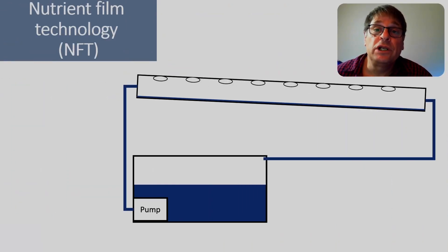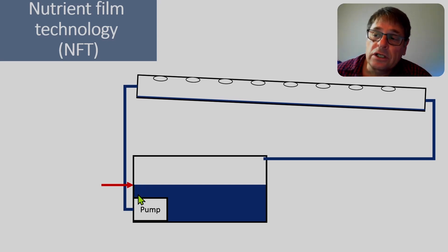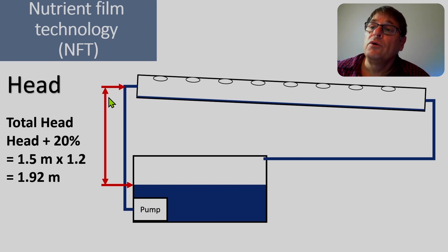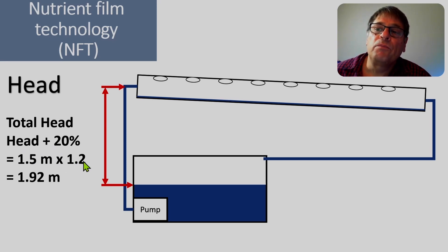Now we need to consider how high we must lift the water in the system. Remember, it's from the lowest point the water can reach up until the highest point where the pump must take the water. If you think your point is a little bit lower, move your measurement from there up to the highest point that the water must be lifted — not the highest point in your system, but the highest point where the water must be lifted to. This gives us our head. In this example, we measured from there to there and found it's 1.5 meters. In order to compensate for the friction in the pipes, we add another 20%, so 1.5 multiplied by 1.2 gives us 1.92 meters. That's the head we'll use to select the pump.